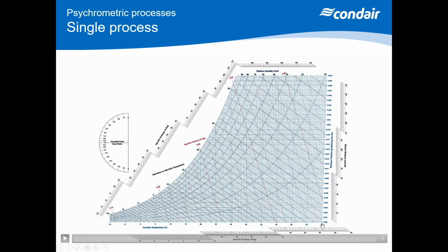Maybe a little bit small for you to see on your screen, but there we go. We go from -10 right up to 60 degrees C. And if you stick a thermometer on the wall, that is the temperature that you're going to read. But there is another temperature scale on the chart, and it's going diagonally down the chart. That's 20 degrees, 21, 22, 23, 24, 25, but 20 degrees wet bulb. So we have a dry bulb temperature and we have a wet bulb temperature, and they're not the same.